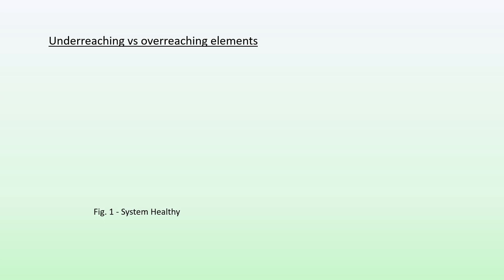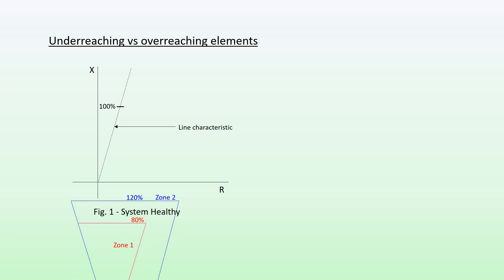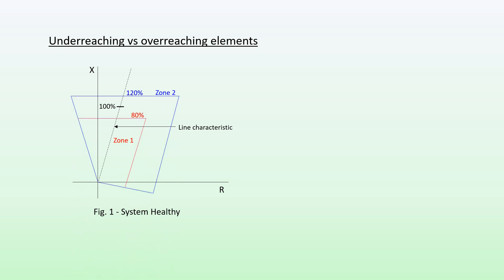Let's start off with a healthy system. We have our impedance plane, and to that we add a distance relay characteristic. The distance from the origin to the hundred percent point represents the impedance of our transmission line. The first dashed line is at a certain angle with respect to the horizontal — that angle being the line characteristic angle.